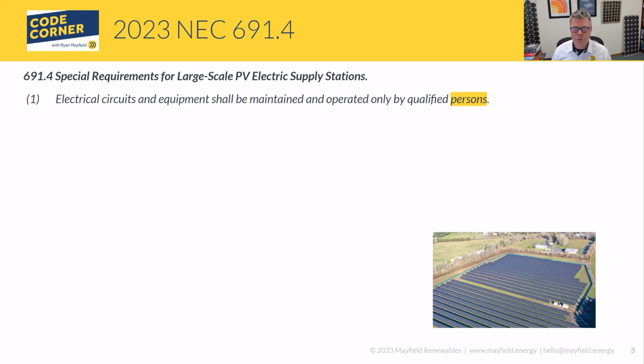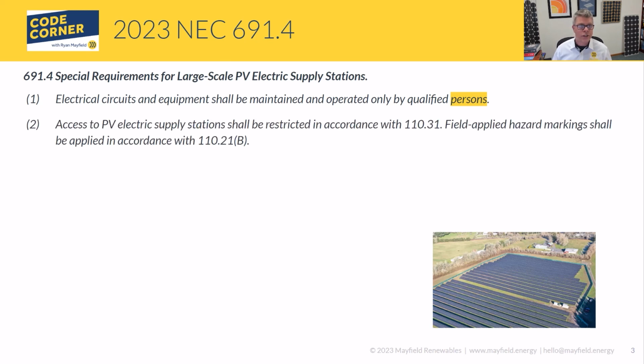That shows up in multiple other code references that you're probably familiar with - it shows up in Article 690 and 706, for example. So nothing new there, but we're making sure this is not accessible to just anybody walking up to it. Access needs to be restricted per 110.31. If you go back to 110.31, it talks about access to components and how we need to provide some level of protection.